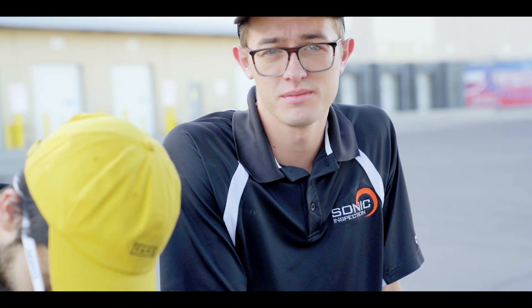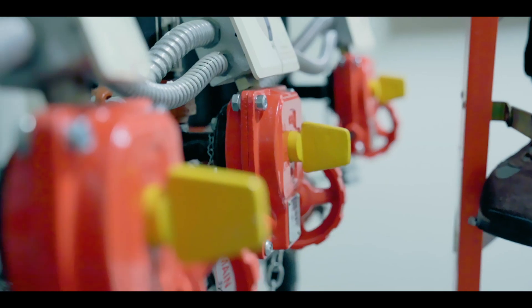Today we're inspecting the fire sprinkler systems for the warehouse. We're here to make sure there's not any extreme levels of corrosion or MIC buildup inside the system so that it can be cleared for their five-year inspection.